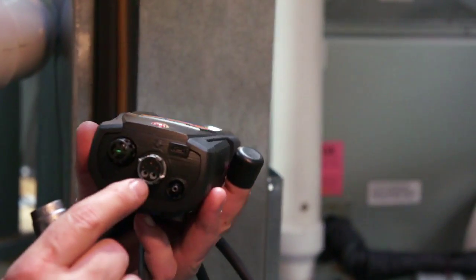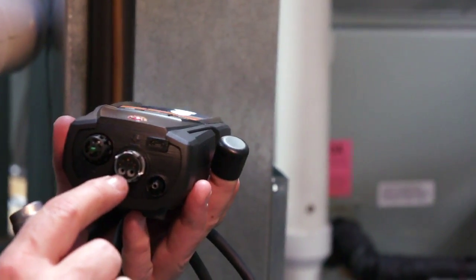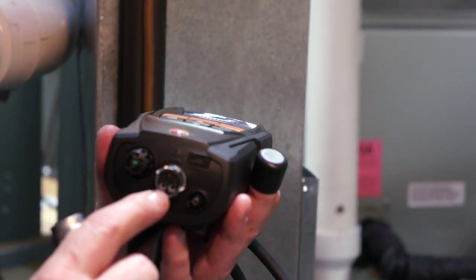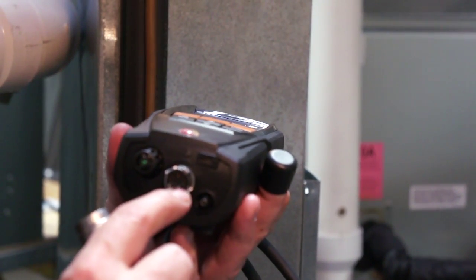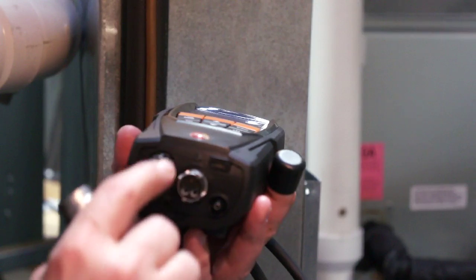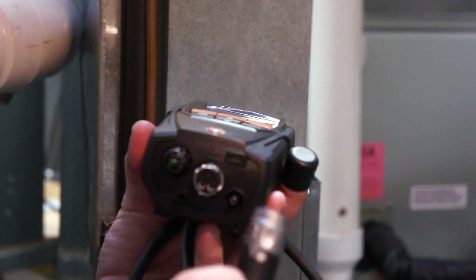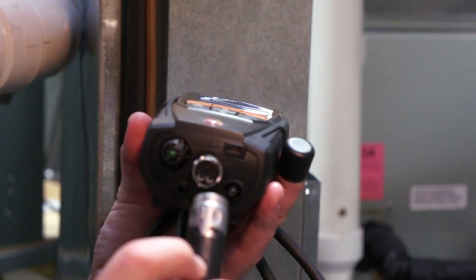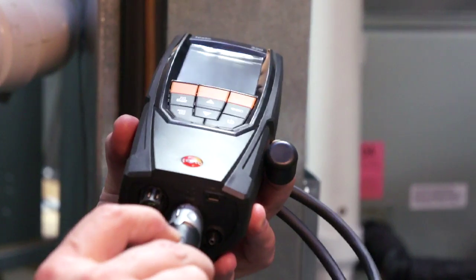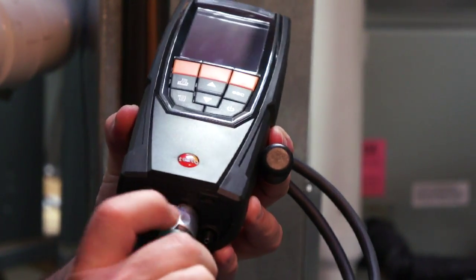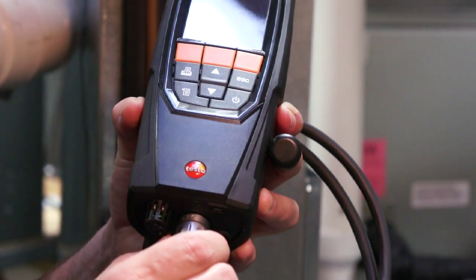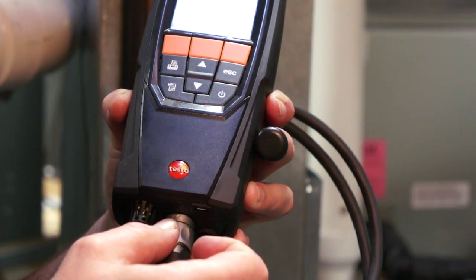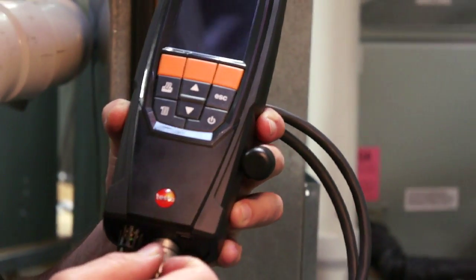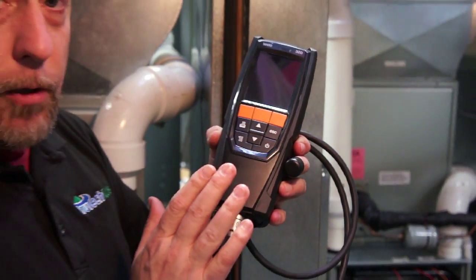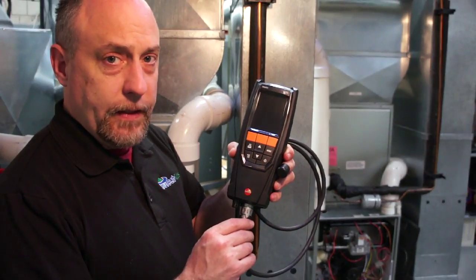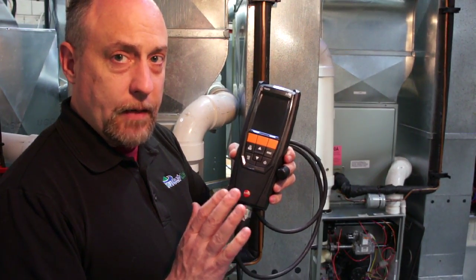Now, the probe assembly on the 320 measures everything. It measures flue gas, draft, and temperature. So I've got to make sure that these two gaskets are sealed tight on the bottom of the instrument. There's an arrow stamped in the housing here and an arrow stamped onto the probe assembly itself. I'm going to line those up arrow to arrow, push that on there, and then the most important part is there's a bayonet clip right here. I want to turn that bayonet clip about 1/8 of an inch until I hear it click, and now I have a positive seal of that probe assembly on the bottom of the instrument. And that's pretty much all you have to do to get that commissioned.